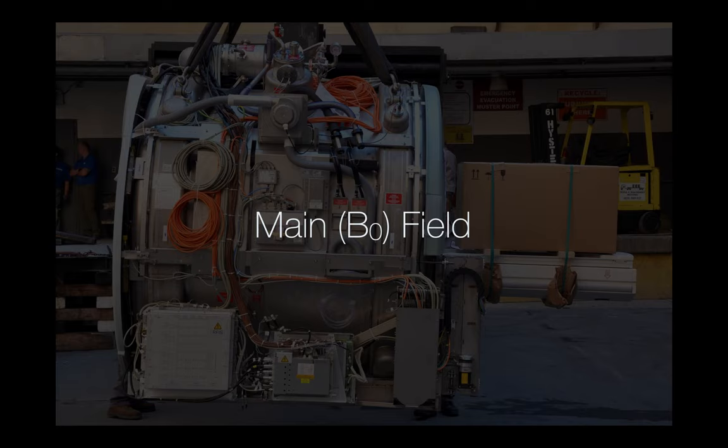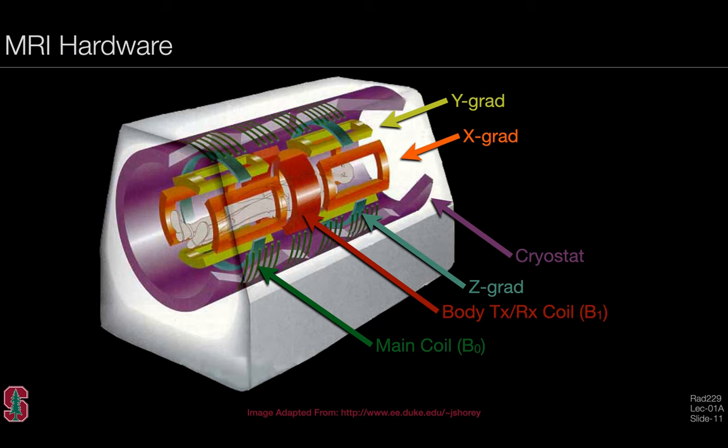Let's talk about the main B0 field. Here's a hardware diagram showing the various important hardware components for a simple MRI system. We're focused on the main B0 field—the electromagnetic windings shown in green that reside inside the cryostat, which is liquid helium cooled to keep things at superconducting temperatures. As the lectures develop, we'll also talk about the body coil, which is the B1 coil used for exciting the spins, and the X, Y, and Z gradients important for spatial localization.